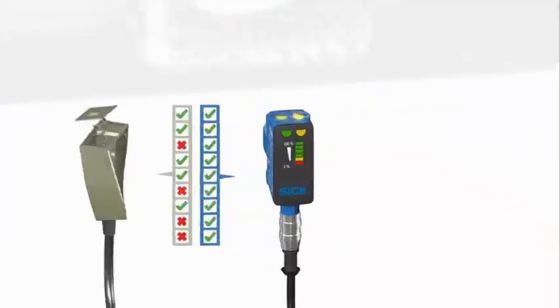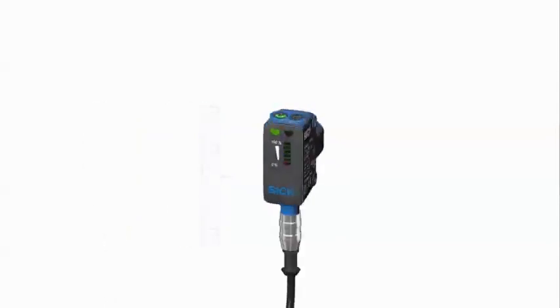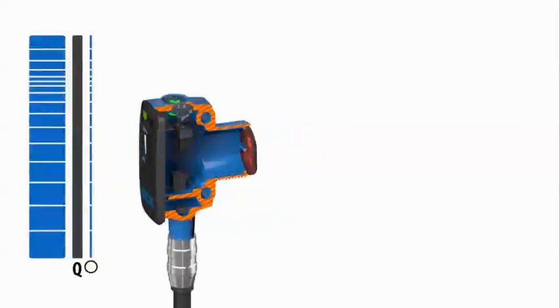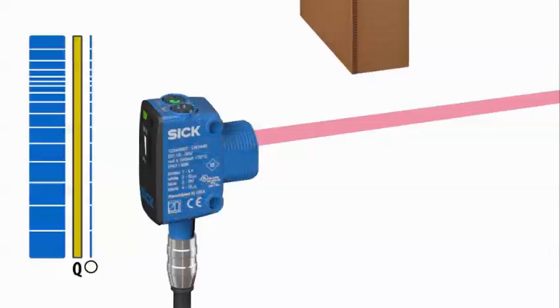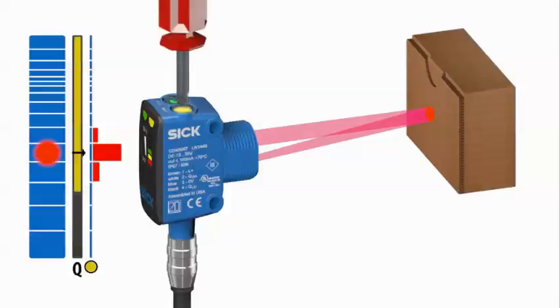SureSense photoelectric sensors solve this issue with superior background suppression technology. It uses a multi-segment receiver array to detect objects by triangulation of light versus traditional approaches based on the amount of light returned to the sensor.